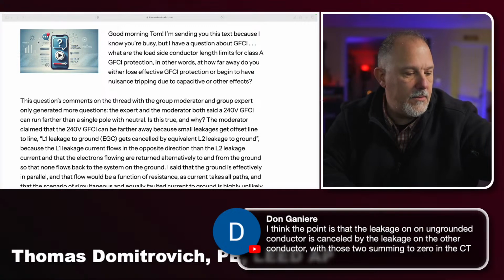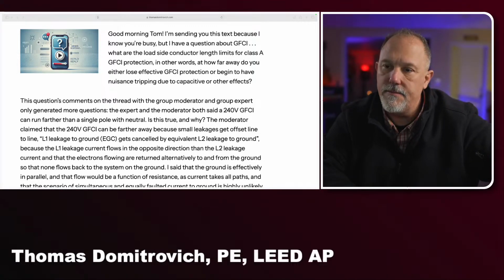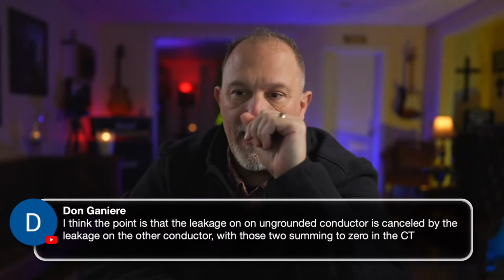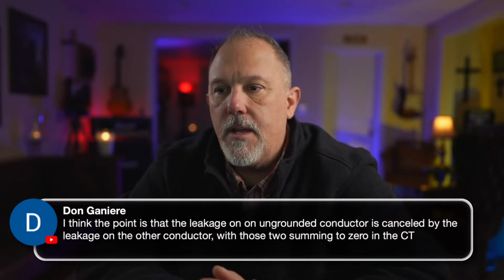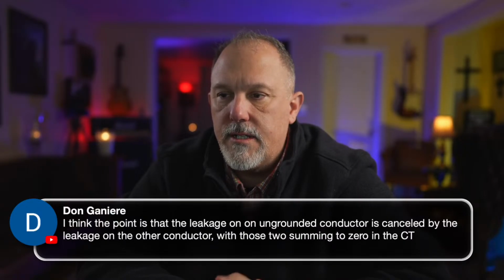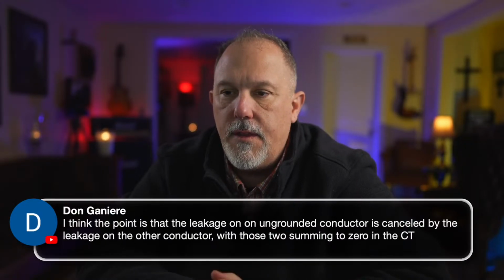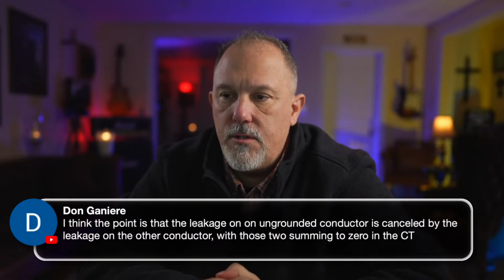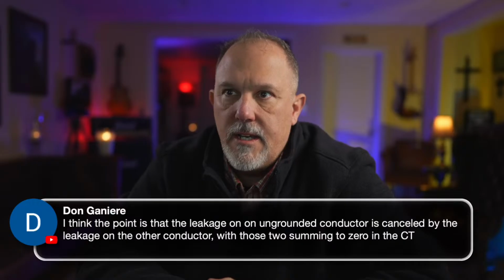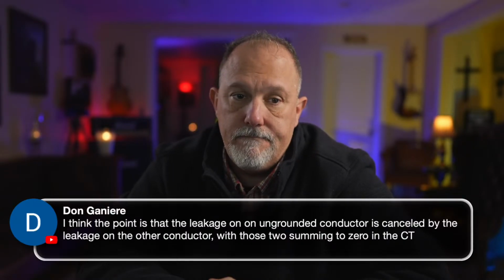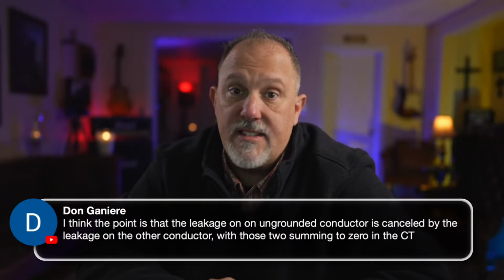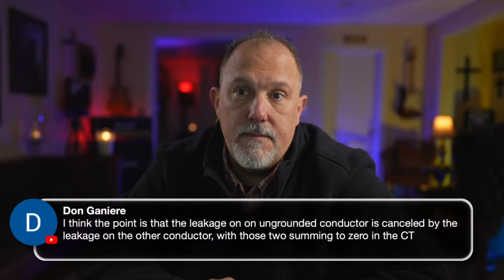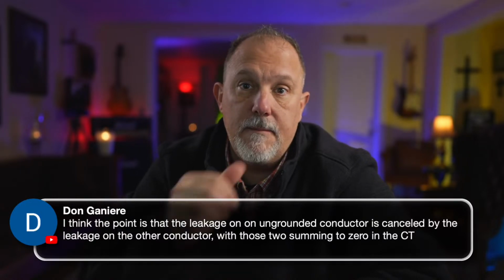Don is saying, hold on, Don. I want to get the whole question up here, or the whole statement. I think the point is that the leakage on the ungrounded conductor is canceled by the leakage on the other conductors, with those two summing to 0 in the CT. It's a theory. I have never seen it in practice.